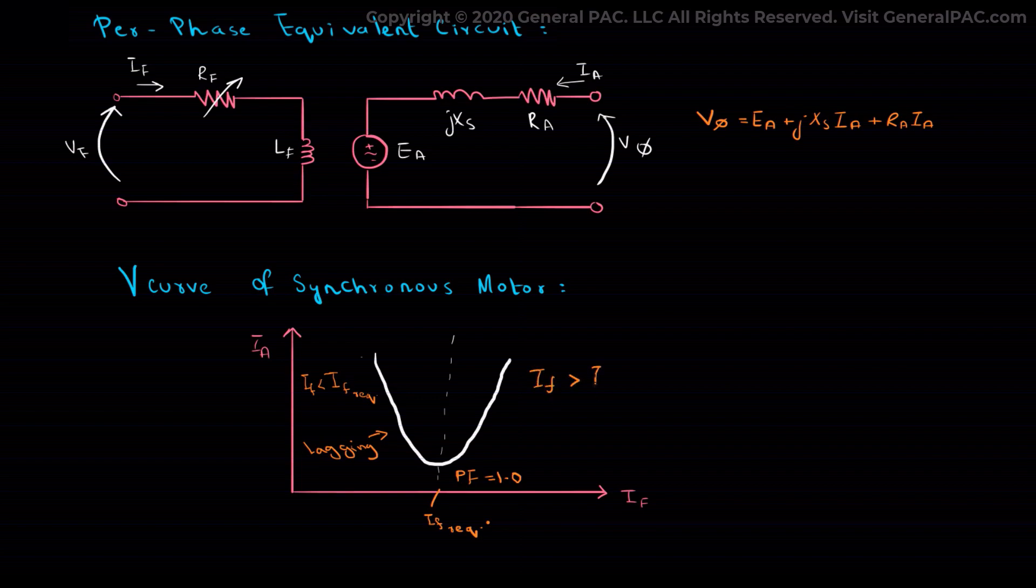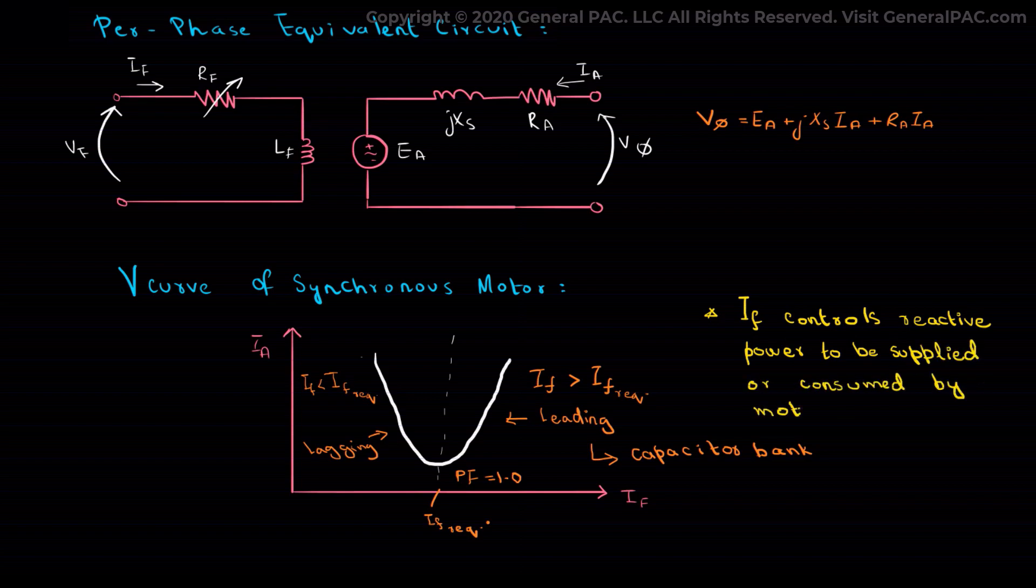But for all values higher than the If which gives us the minimum Ia, Ia is leading and reactive power is supplied by the motor, i.e., the motor acts as a capacitor bank. So we can conclude here that the field current controls the reactive power to be supplied or consumed by the motor.